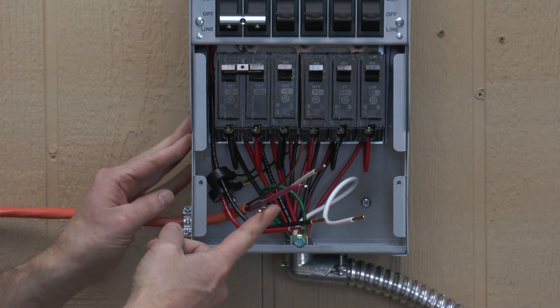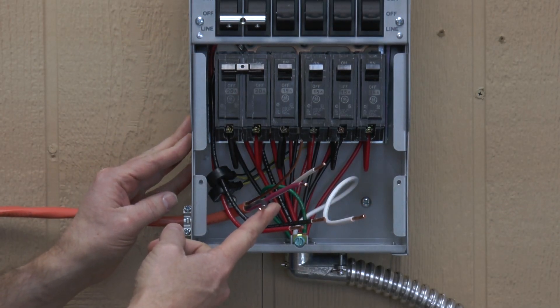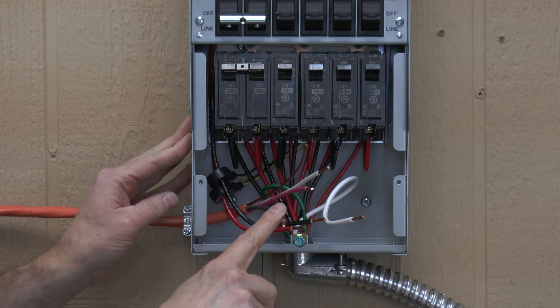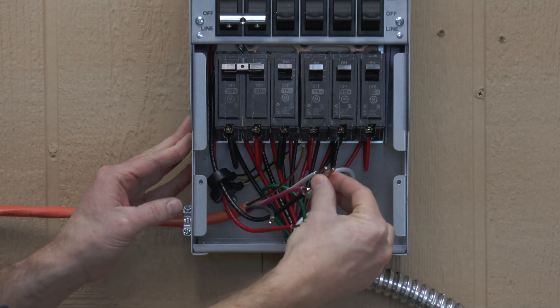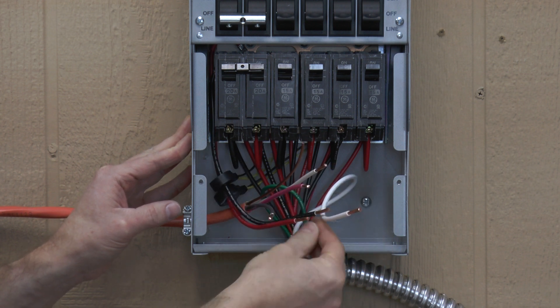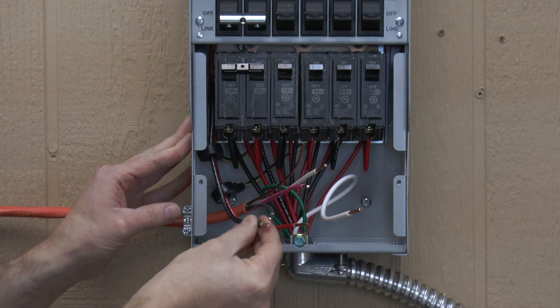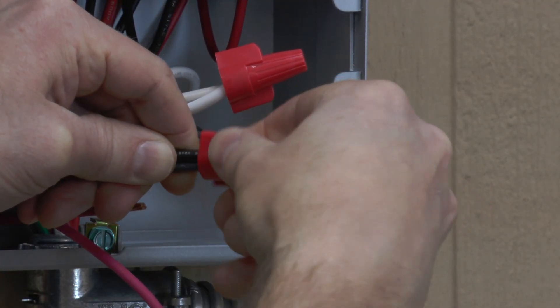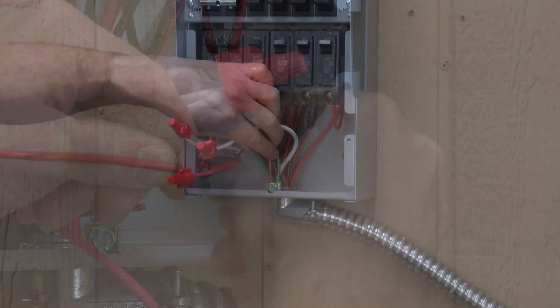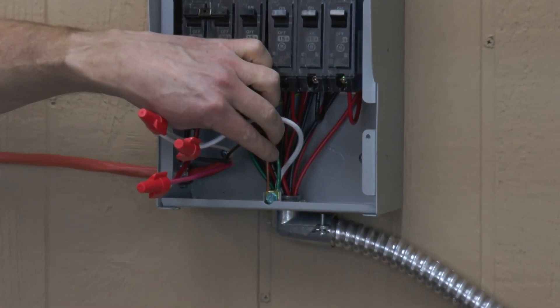Be sure to leave plenty of wire inside the transfer switch. Cut back the insulation and strip the wires for wire connectors. We're going to connect white to white, red to red, and black to black. The bare or green wire should be connected to the ground terminal.